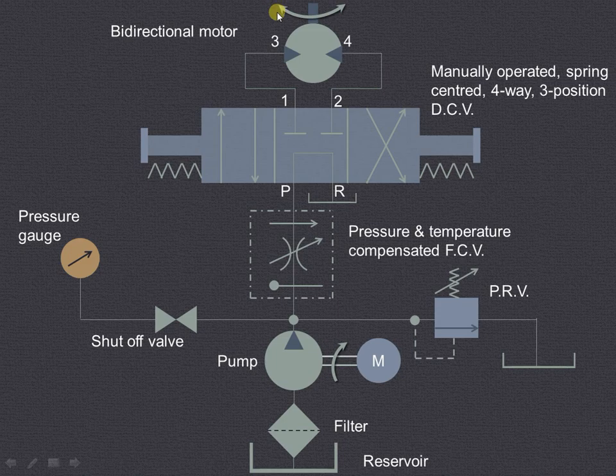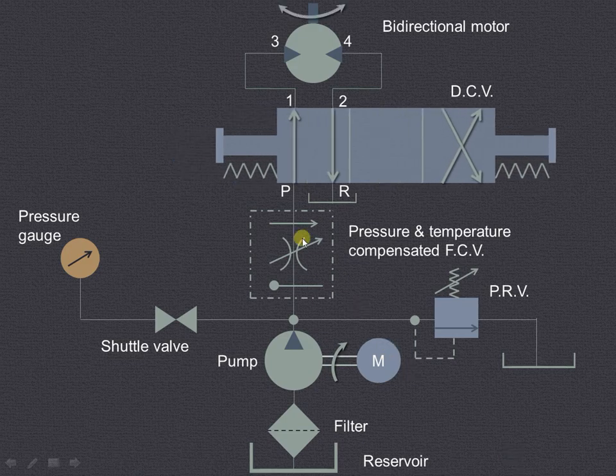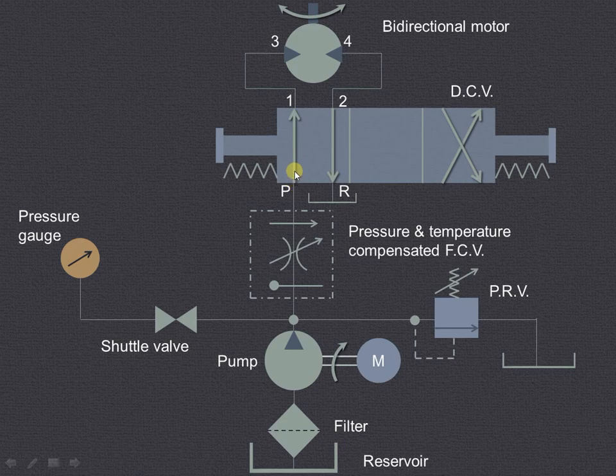Let us see what will happen when we move this direction control valve to get the left envelope mode. The liquid will be pumped from the reservoir through the filter. It will enter into the pressure and temperature compensated flow control valve, and as the variable restriction is provided, a controlled rate of liquid will be allowed to enter into port P. From P it will enter into port 1, then from 1 it will go to port 3 and rotate the motor in the given direction. The liquid from the other side — from port 4 — will enter into port 2, from 2 to R, and then go to the reservoir.